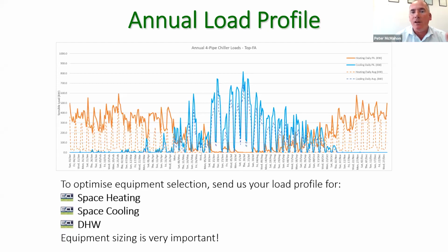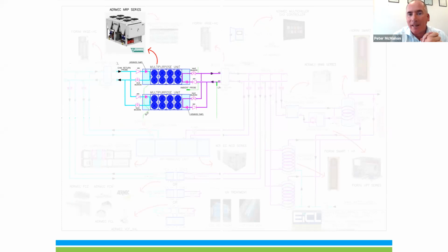So we need to consider what's your actual space heating load, what's your space cooling load, and if you have a domestic hot water load. And if you have a load profile, absolutely brilliant. Some of the engineers in HVAC applications can give us that. I'm not quite sure about a lot of you guys if you can give us that information or not. I know one of my colleagues, Patrice, has worked with possibly some of you guys on here today. And we have managed to calculate loads and work with you very closely on that. So that's the first component I want to tell you about, the multifunctional heat pump. It is all about recovering that energy, and that's obviously what this series of presentations is about, I'm led to believe.